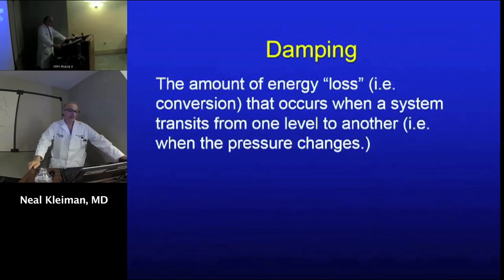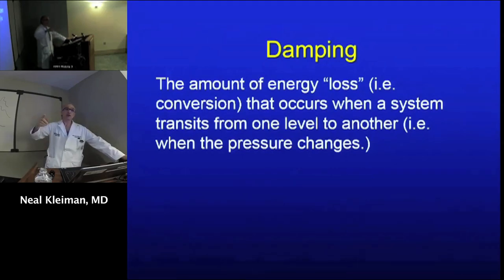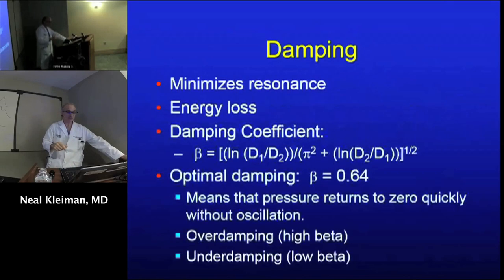Damping is technically defined as the amount of energy loss, and energy is not lost, energy is conserved. It's the conversion of energy between forms, between potential and kinetic energy, that occurs when a system transmits from one level to another, meaning when the pressure changes. So if you want to measure static pressure, you'd be okay damped. But as the pressure changes, energy is transformed into a form you can't measure unless you have microprobes that can measure trivial changes in the temperature of your measuring system.